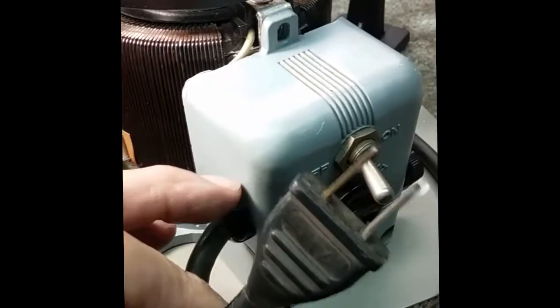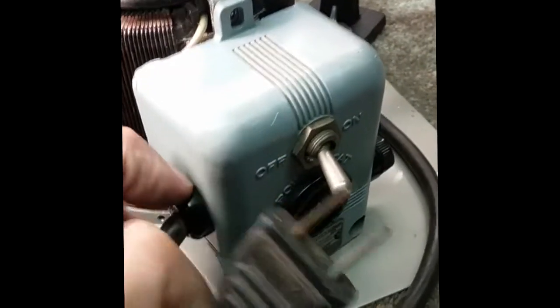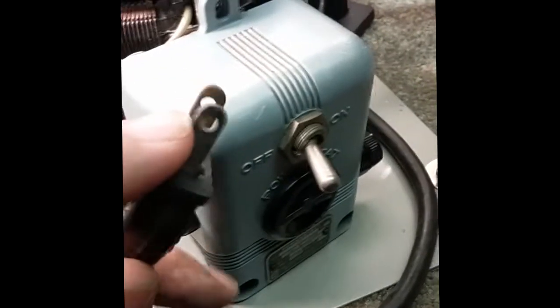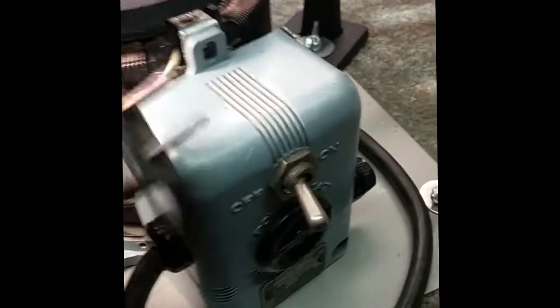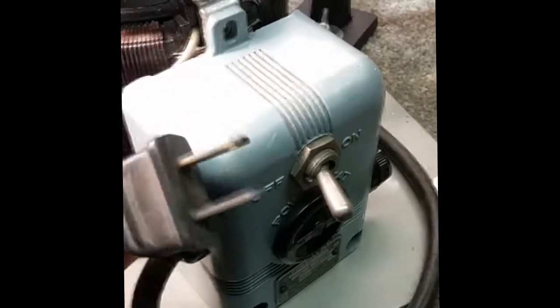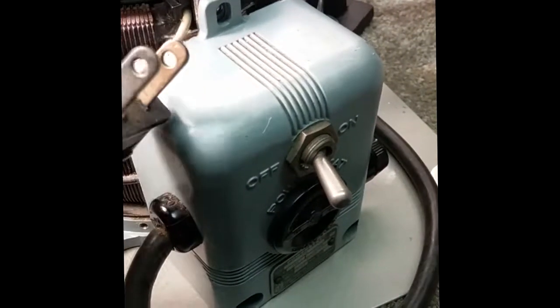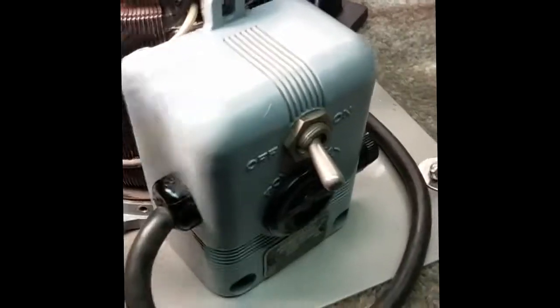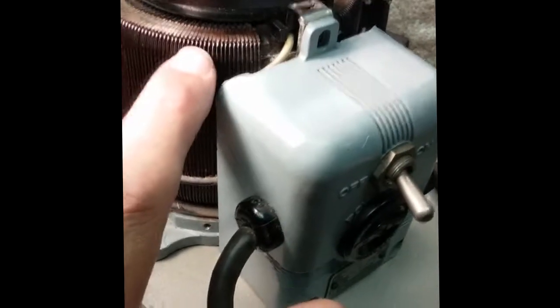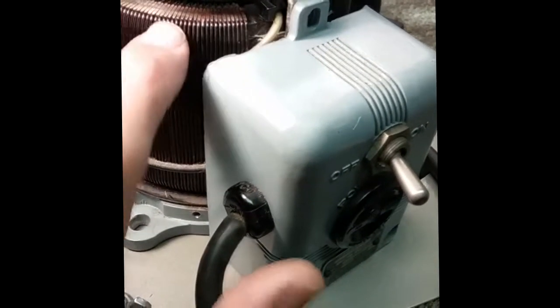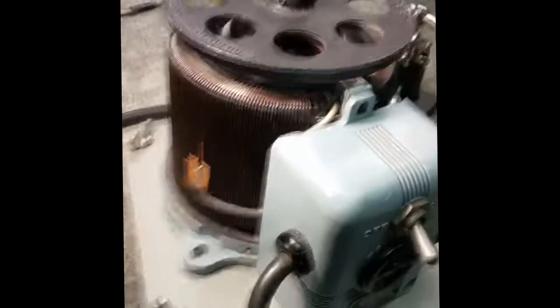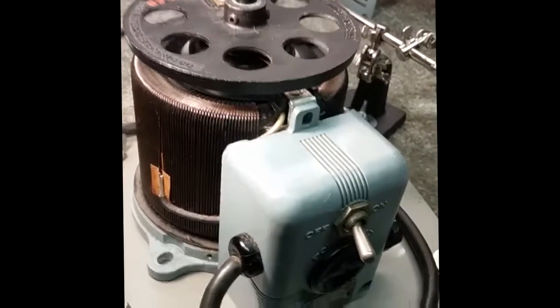It is not an isolated transformer. None of these are. That's a mistake a lot of people make. They think that rheostats are isolation transformers. They're not isolation transformers. That neutral is actually passed through. And they're not grounded. So, be aware that you're running right off the 120 line. This coil goes across the 120 mains. So you're not isolated in any way by using a rheostat. You need an isolation transformer in addition.